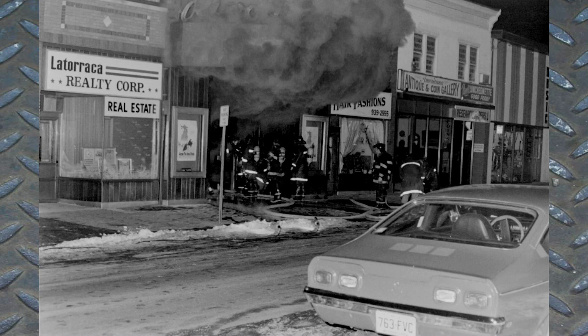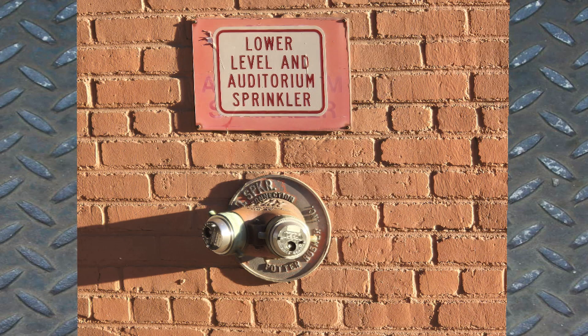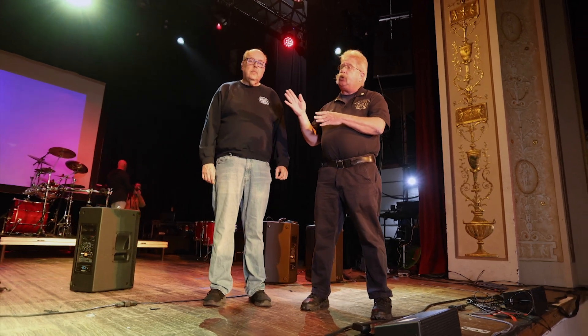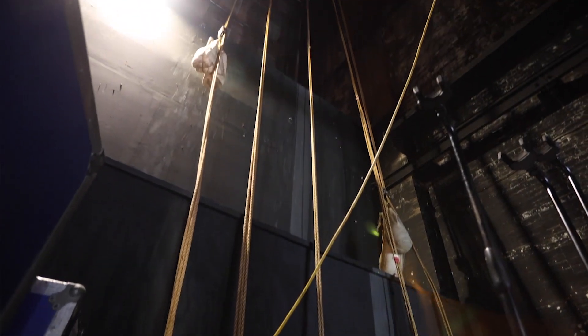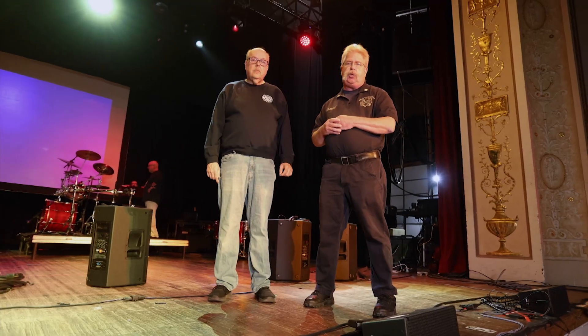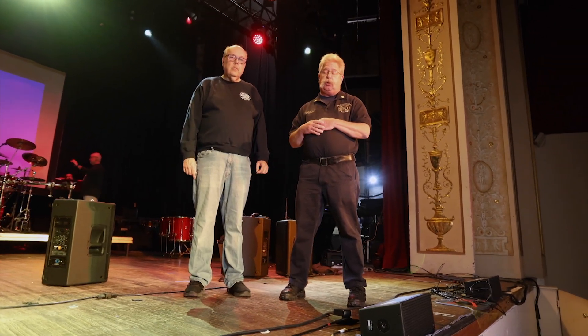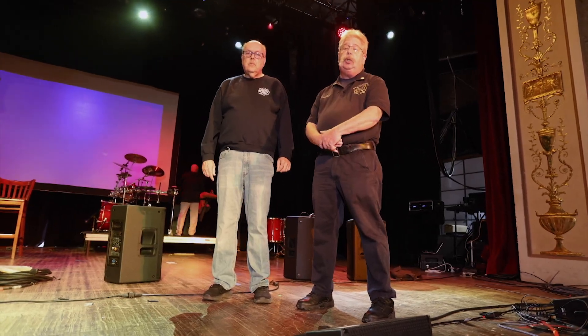As part of the post-fire renovation, an automatic sprinkler system was installed throughout the building. Also part of that renovation, the area behind the stage house and to our right had six stories of wood-framed dressing rooms and storage areas. The post-fire renovation demolished those six stories of wood-framed construction, significantly reducing the combustible fuel package behind the proscenium arch and proscenium wall. Today there are two stories of dressing rooms with wood-framed drywall finishes, reducing the fire threat behind the stage.